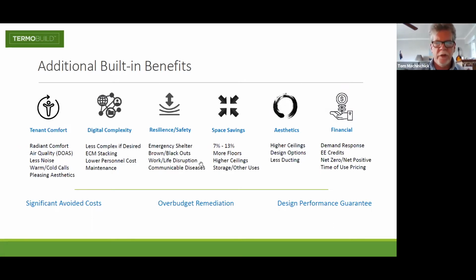So for the designers, architects, and engineers of the buildings, there's space savings up to 7 to 13%. This means that with the concrete hollow core flooring slabs being used as part of the ventilation, drop ceilings are not necessary anymore. So you can lower the height of the floors, but still have the same height of the ceiling if desired.